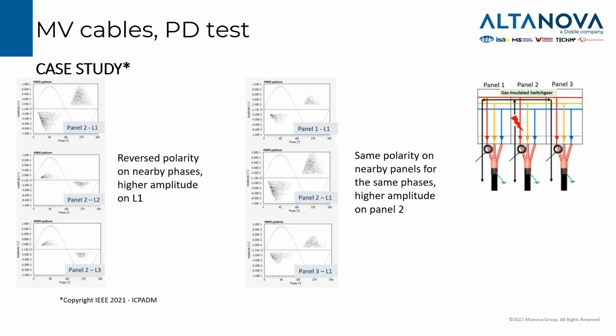There is also a rough analysis of the case study on this slide. On the left, we can see the test related to the HFCT on the three phases of the panel number 2. And we can see that there is a higher amplitude on phase L1 and reverse polarity for L2 and L3. Instead, on the column on the right, we have three PRPD patterns related to the test performed with HFCT on phase L1 for panel 1, panel 2, and panel 3. So we can see that when we have a reverse polarity on nearby phases, we can recognize the phase source. Instead, when comparing the data from the three different panels, we can localize the panel that is the source of the PD.